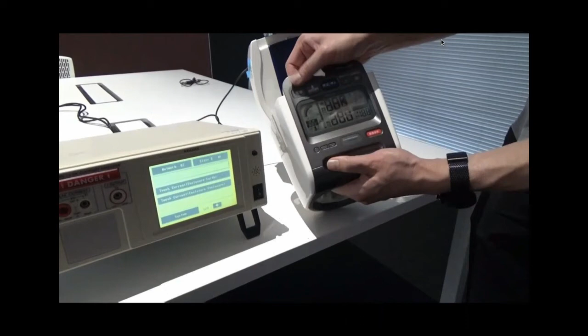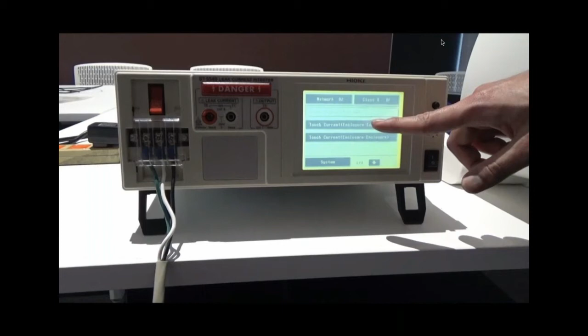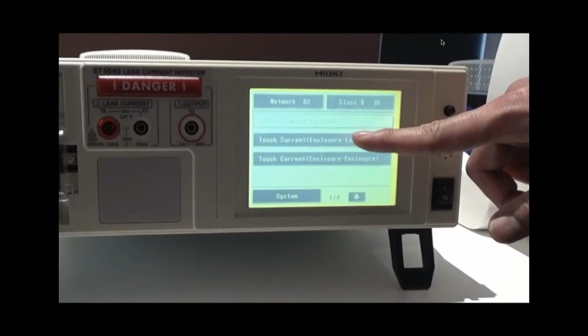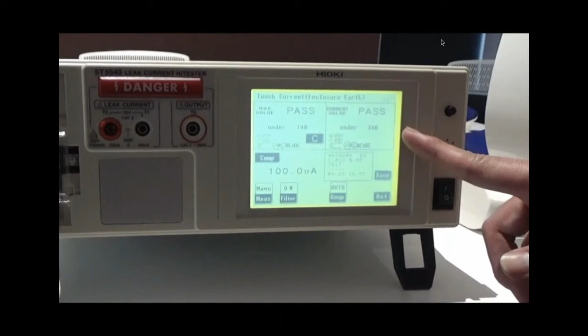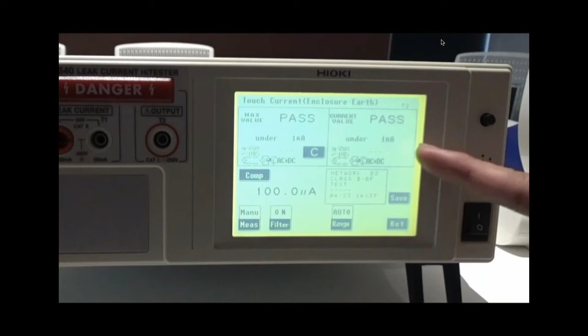At first, I supply power to the medical equipment from here and check to see if it's turned on. It is powered on and running. Now I will measure enclosure leakage current or touch current. When a measurement item is selected, it starts the measurement. The left screen shows the maximum value and the right screen shows the current measurement value.